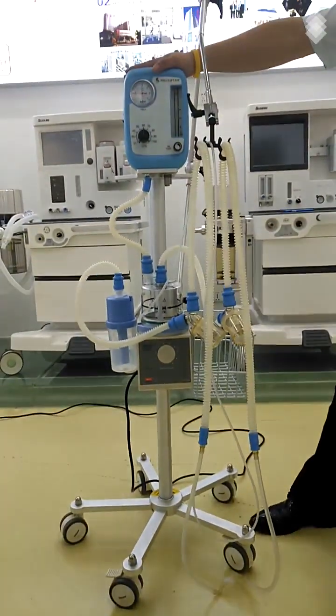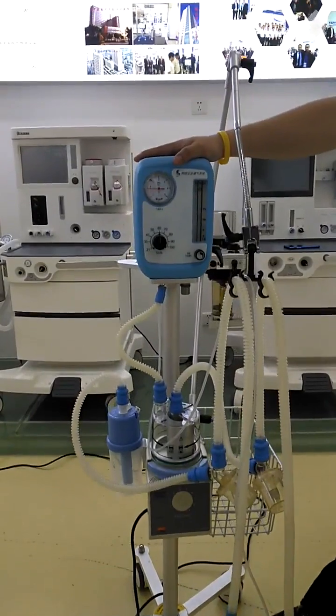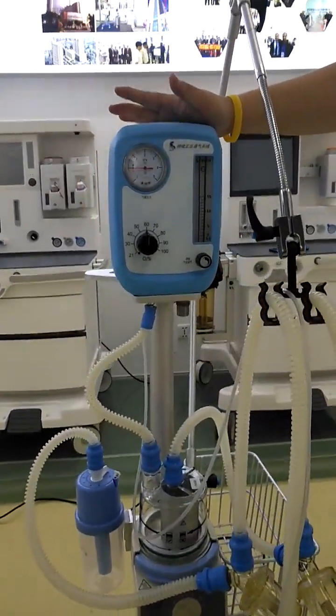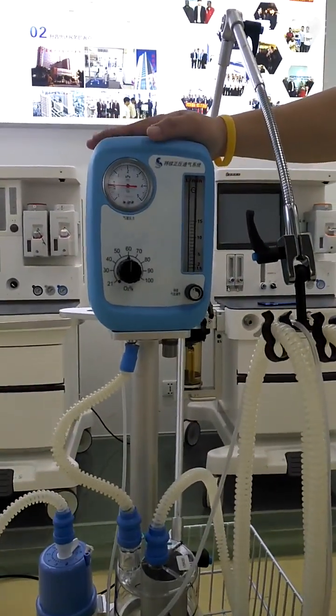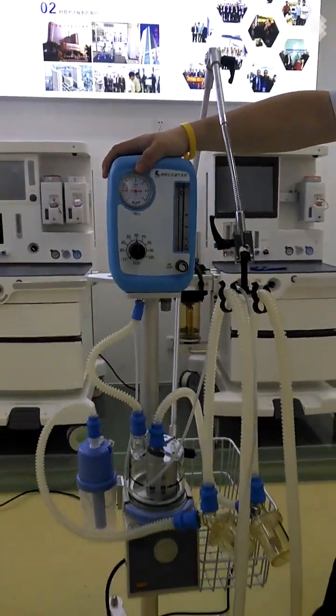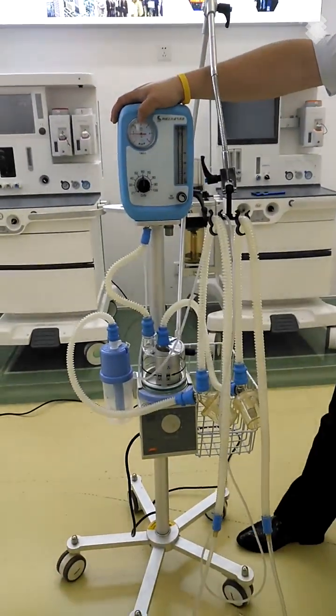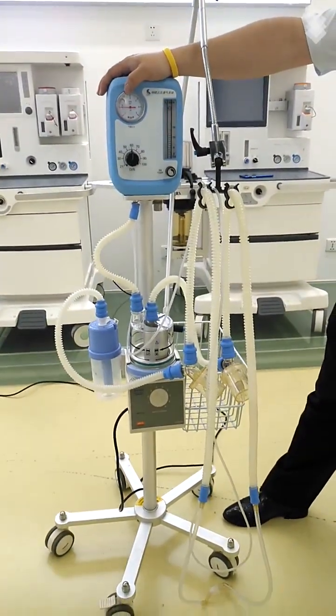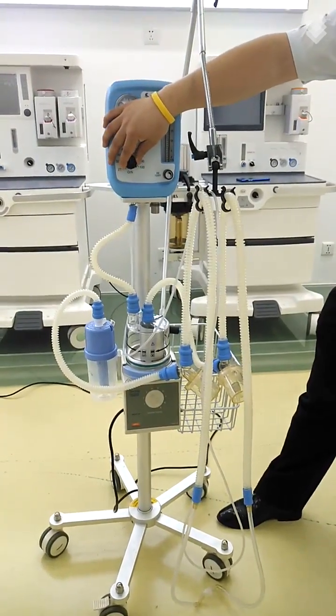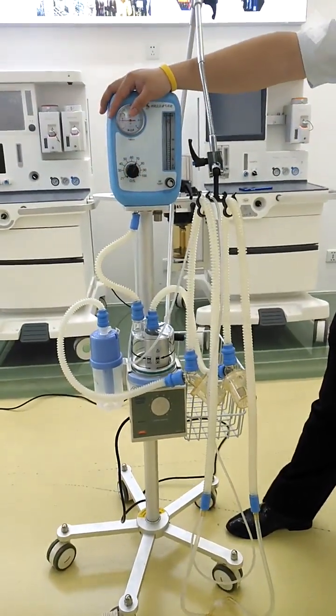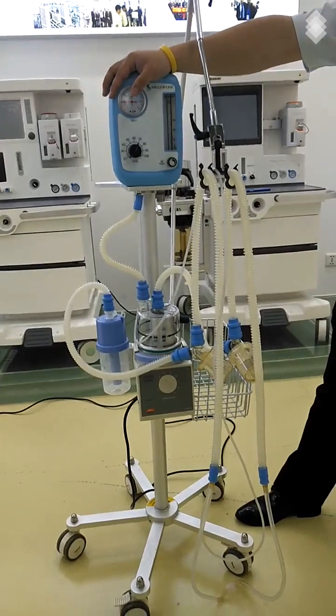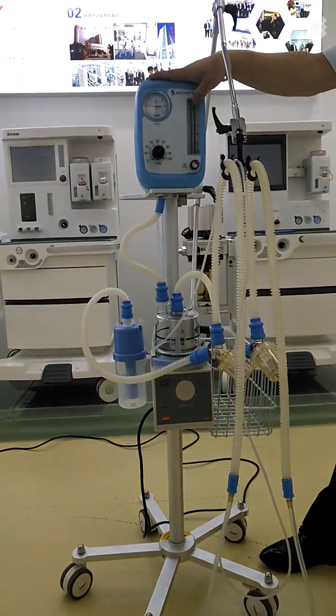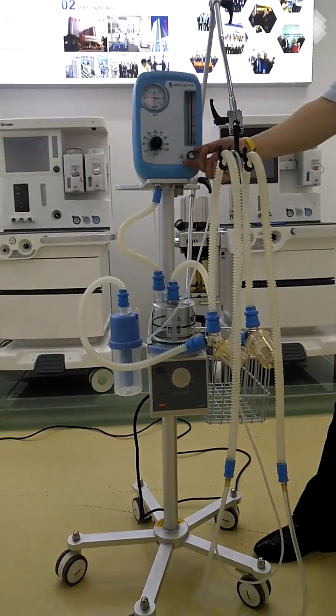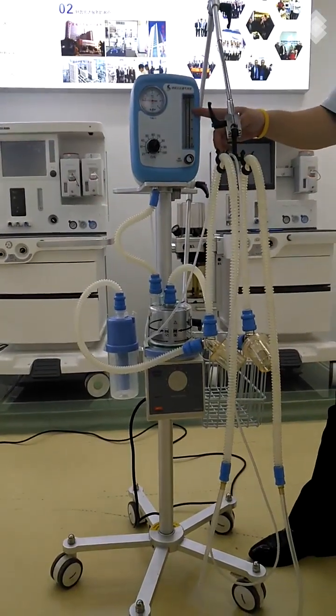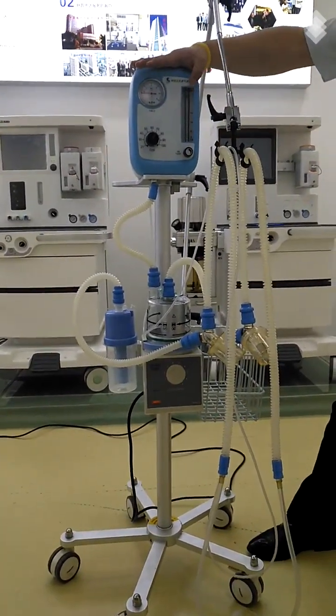On the main engine, for this model we don't need to use the battery or the AC power. It's a mechanical ventilator. So, as you can see, it's very simple. Here is the pressure meter for monitoring the pressure, and here is for adjusting the oxygen concentration, which goes from 21% to 100%. And here is the flow meter. With the flow meter we can adjust and also monitor the flow. This is for testing the flow.